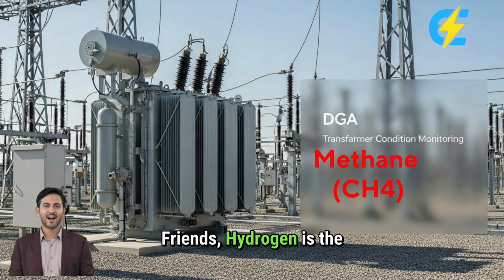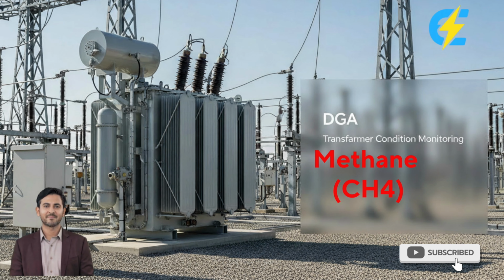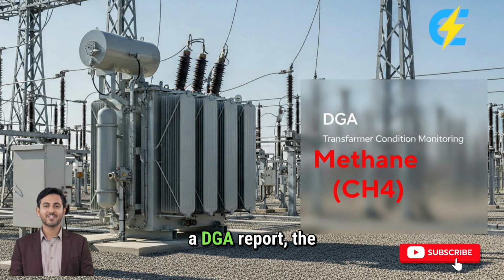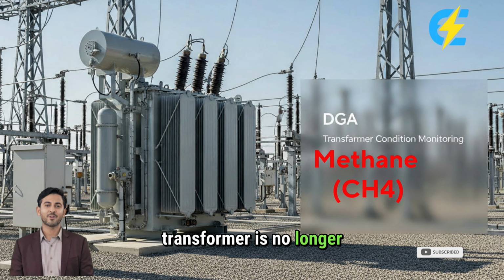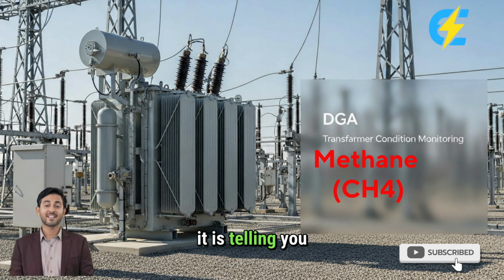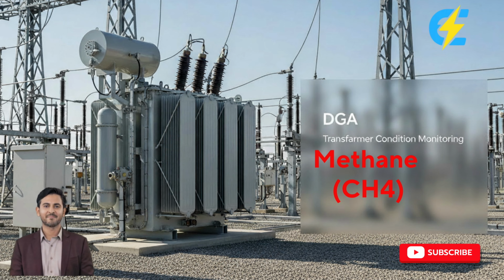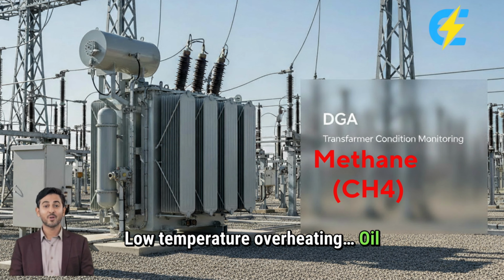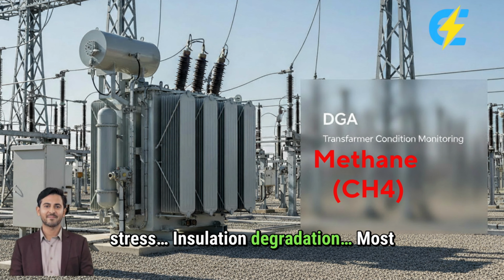Friends, hydrogen is the first whisper, but methane is the confirmation. When methane appears in a DGA report, the transformer is no longer just warning you. It is telling you where the problem is starting. Low temperature overheating, oil stress, insulation degradation.